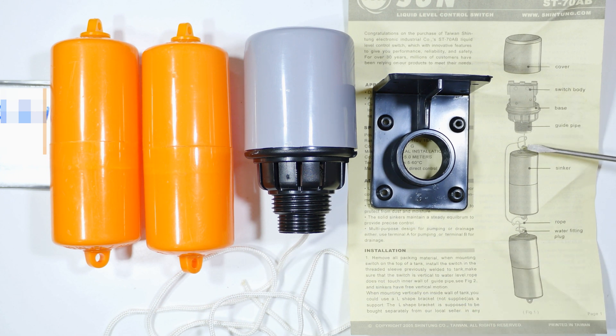When both of these floats are out of the water, they are heavy enough to pull down on the switch. It has both normally open and normally closed positions so it will activate. When they are both underwater, they are light enough that the mechanism will pull up and take the switch in the opposite direction.